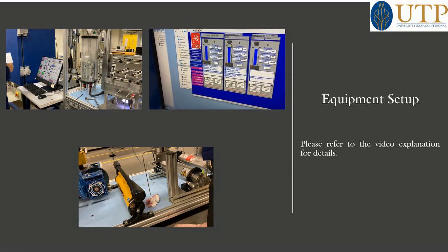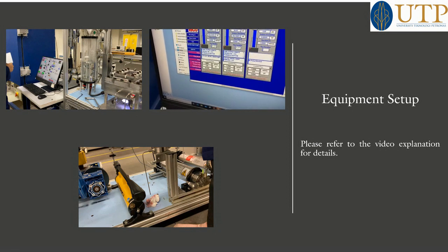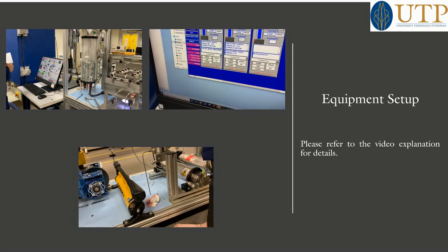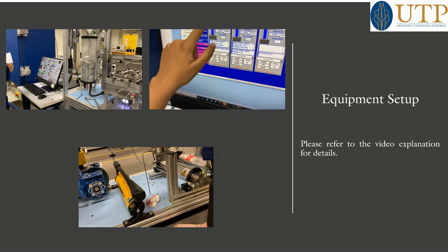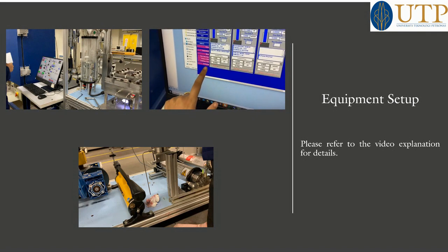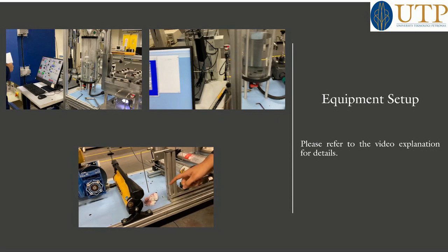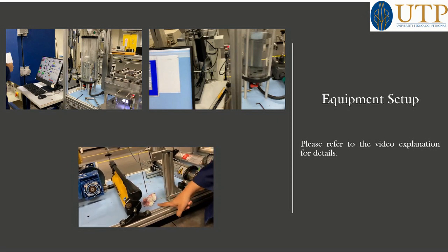That's why it's remote. Now change it to constant flow, and this one constant flow, and the flow rate is like 0.5 ml per minute, and only start for pump A, not for pump B. Only start for pump A. Okay. So when I start it, now we can see the fluid is coming. That means our line is totally okay.